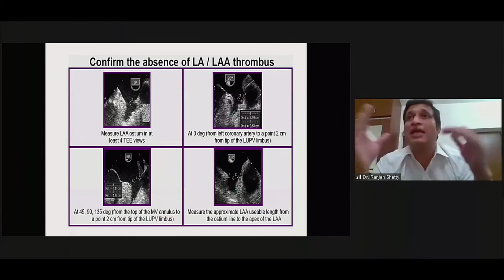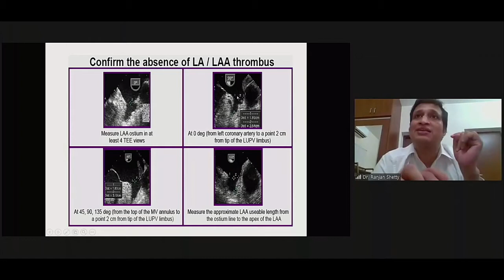But if you're taking a device which would sit on the neck, that would be ACP, Amulet, or the Lambre, the measurement would be different. In which case, we would measure somewhere here. You would measure the ostium, you would come 10 millimeter in. That's where most of these devices will sit, and you will measure here. So the point I'm trying to make is, it's not one number, there are many numbers. So those numbers come based on the device you choose.